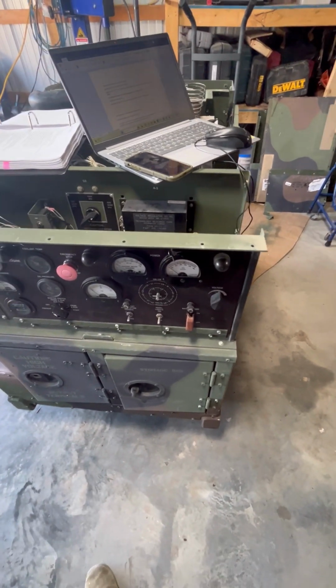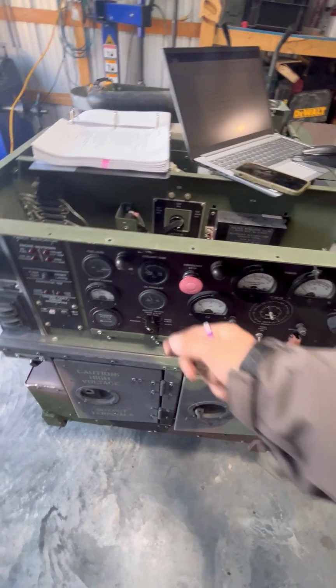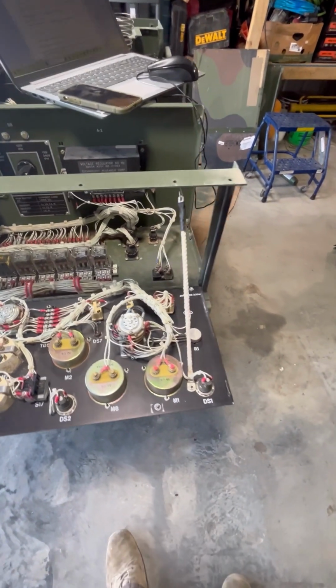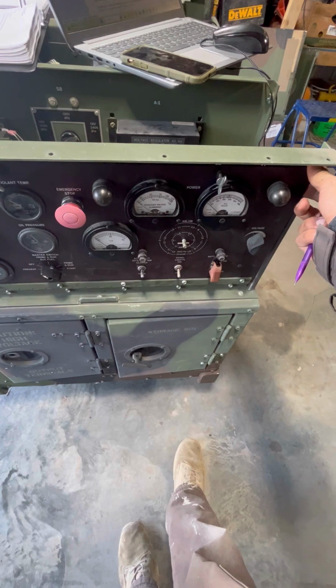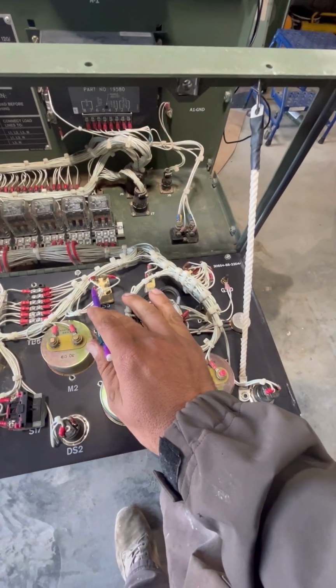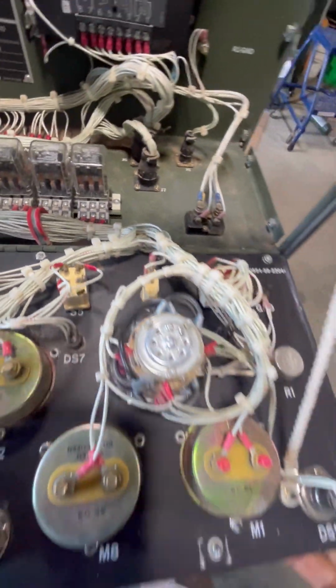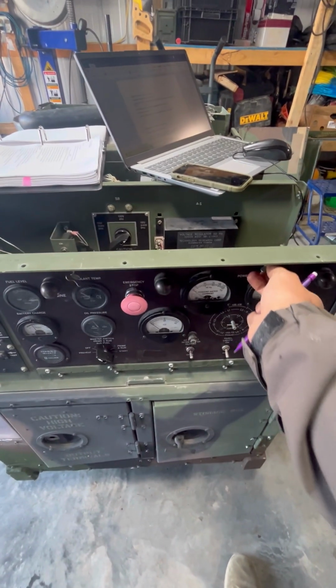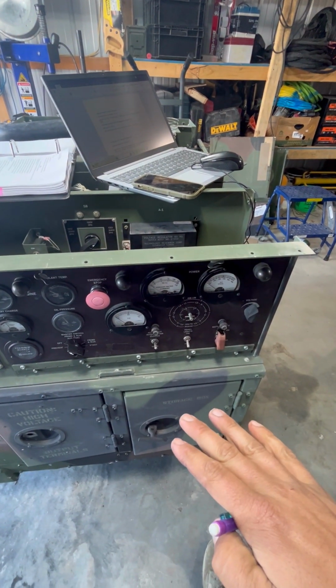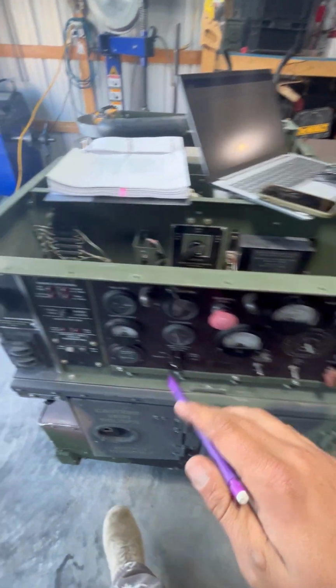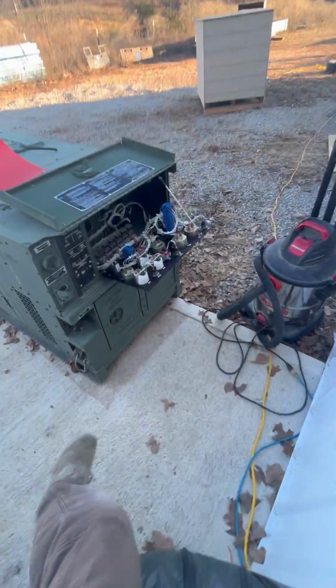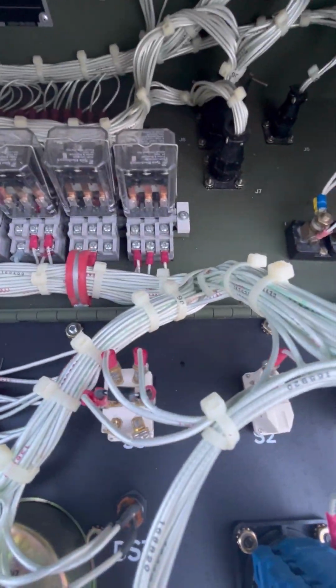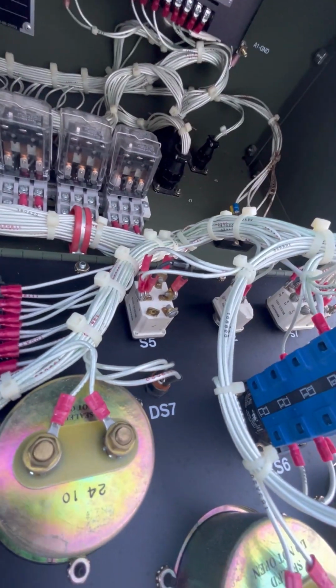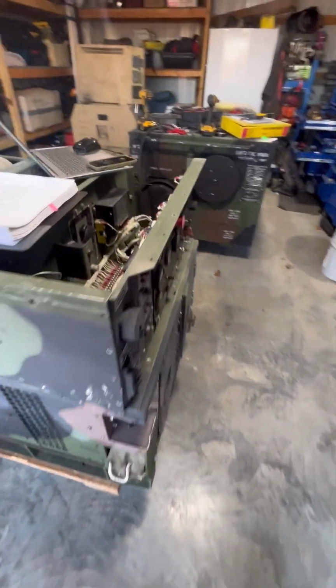So I got back on Steel Soldiers, and I did a little bit more reading. In a particular forum, one of the main members asked somebody who was having a similar issue, does your interrupter circuit switch have a diode between terminal 2 and terminal 5 of the S5 switch? As I was reading that, I was like, hold on a minute, I know mine doesn't. So I ran over here to my MEP-802. I opened up that one, and that one, in fact, does have the diode between leg 5 and leg 2. I pulled that diode off. I put it on this generator, and it fired up.